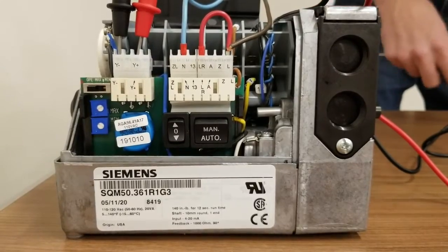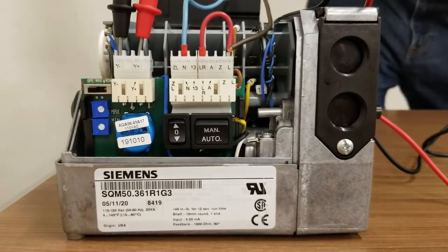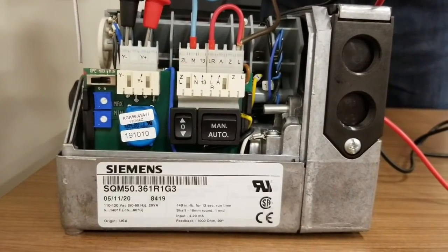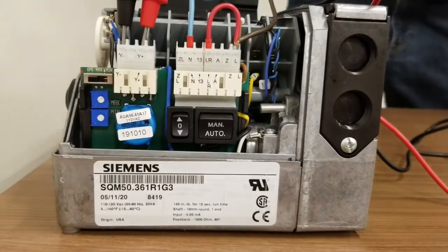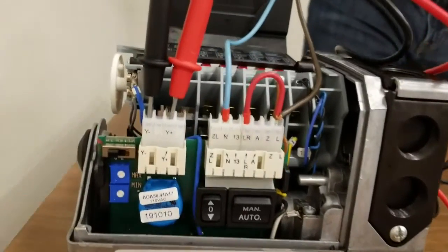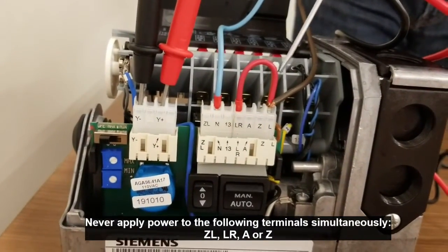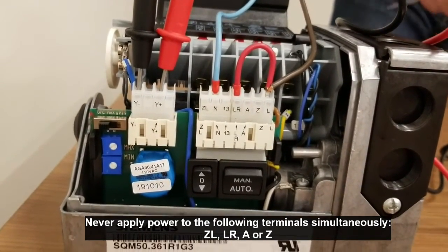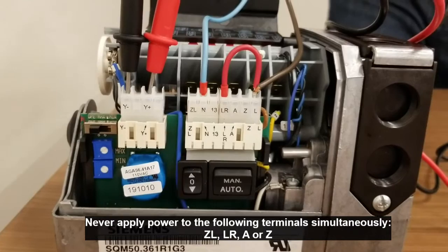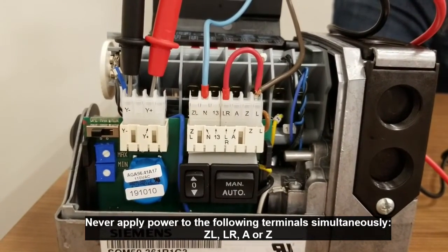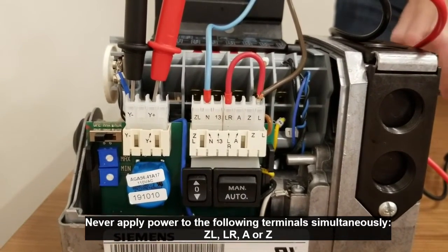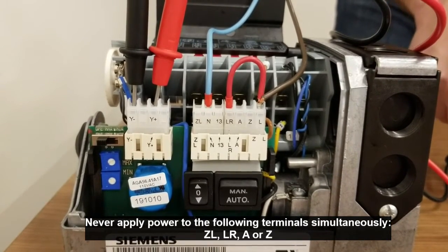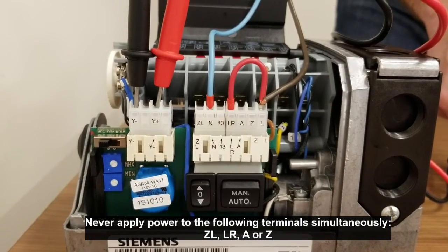So here we have the actuator wired up. First thing I want to point out is that this OPE max min switch is set to the OPE position. And you'll also notice that I have line voltage on the LR terminal here. It's very important to note, you do not want to power multiple input terminals at once. You do not want power supply to the A, Z, ZL, or LR terminal simultaneously. Only one of those terminals should be powered at once.